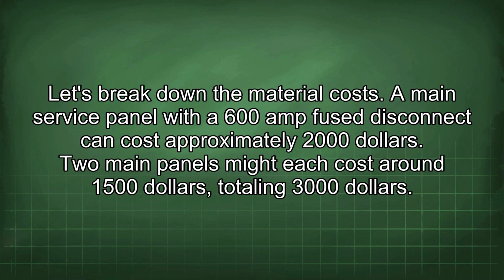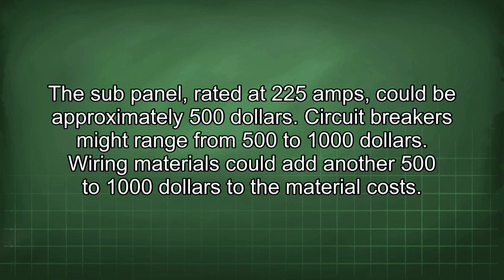Let's break down the material costs. A main service panel with a 600 amp fused disconnect can cost approximately $2,000. Two main panels might each cost around $1,500, totaling $3,000. The sub-panel, rated at 225 amps, could be approximately $500. Circuit breakers might range from $500 to $1,000. Wiring materials could add another $500 to $1,000 to the material costs.